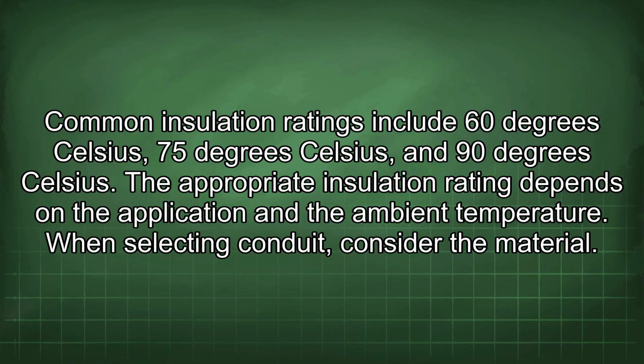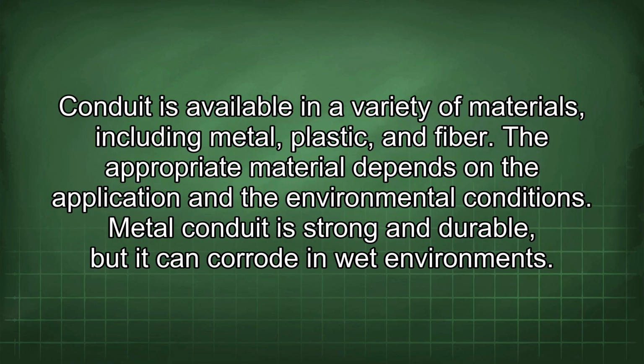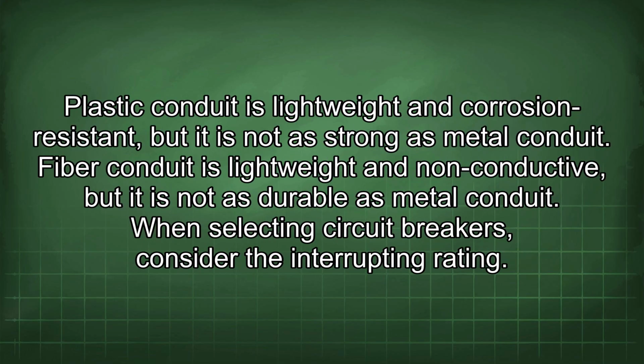When selecting conduit, consider the material. Conduit is available in a variety of materials, including metal, plastic, and fiber. The appropriate material depends on the application and the environmental conditions. Metal conduit is strong and durable, but it can corrode in wet environments. Plastic conduit is lightweight and corrosion resistant, but it is not as strong as metal conduit. Fiber conduit is lightweight and non-conductive, but it is not as durable as metal conduit.